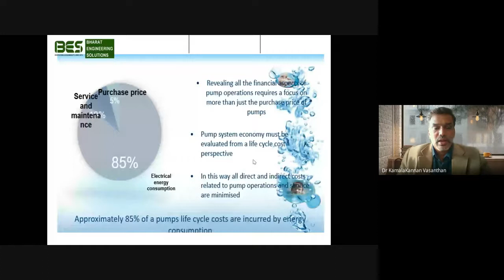The second major reason we see with regard to excess power consumption in pumps is improper selection. Normally, if you approach any dealer, distributor, or manufacturer, there will be some ready-made system available for a particular running flow and head, and that model gets supplied whenever a particular flow and head requirement is raised. For example, this model, CR45-4-2, is manufactured for a flow of 42.6 meter cube at a head of 75.3 meters, with an ETA pump efficiency of almost 76.9%.